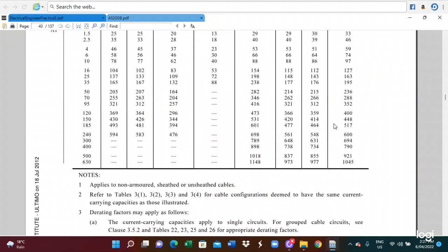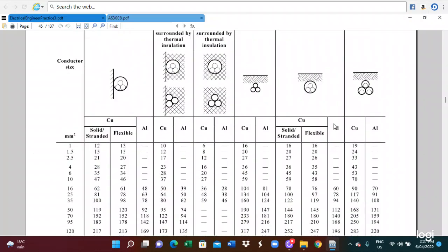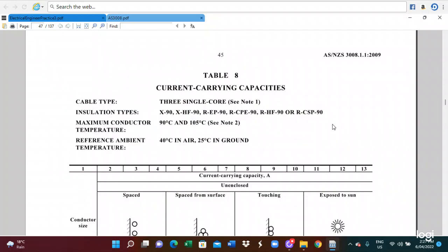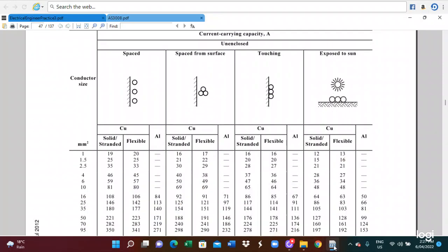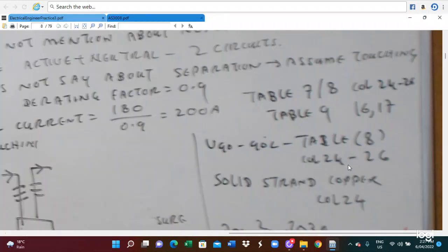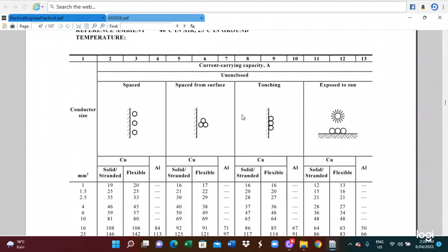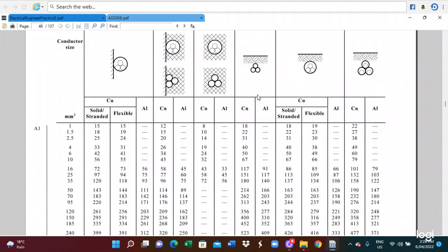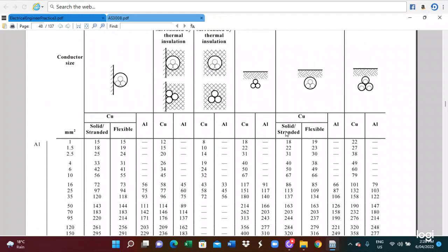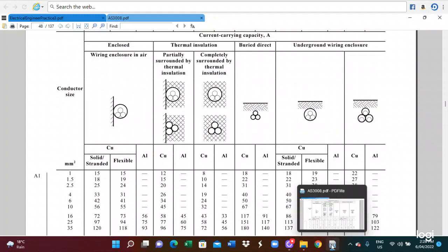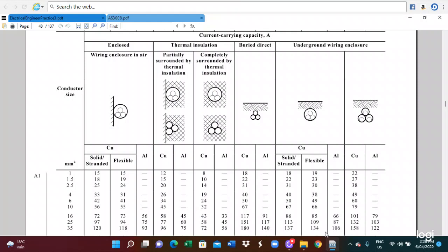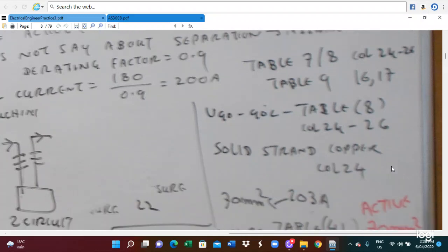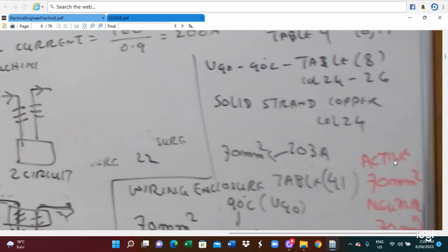Table 8, column 22 to 24. So this is table 8, column 24 to 26. You refer to the column, here it is 24 to 26. In this case, we use a solid conductor, so we have to use column 24. Okay, column 24 we got. And also we have to find table 22, which is the derating factor. For the derating factor, we have to refer to table 22.